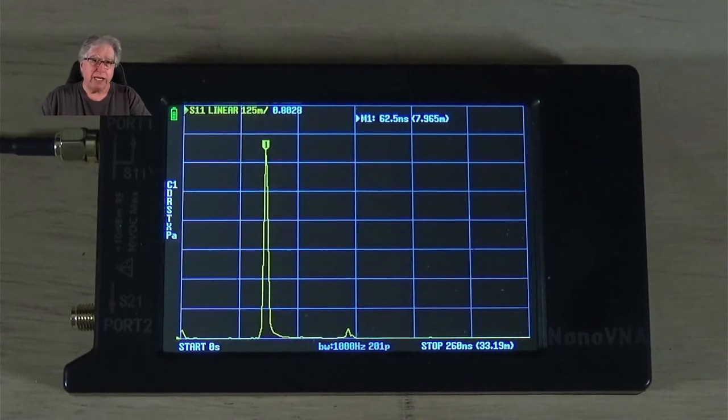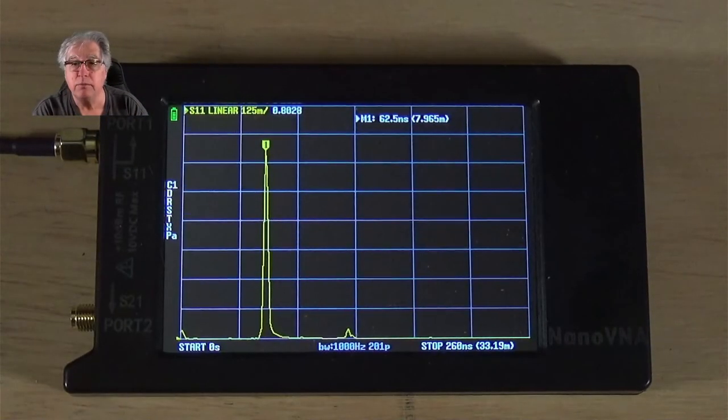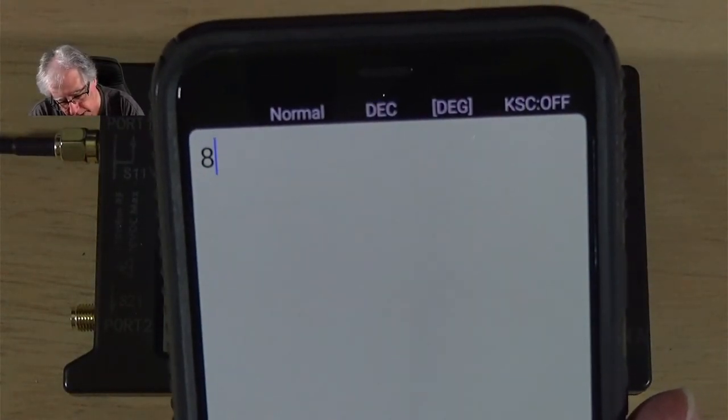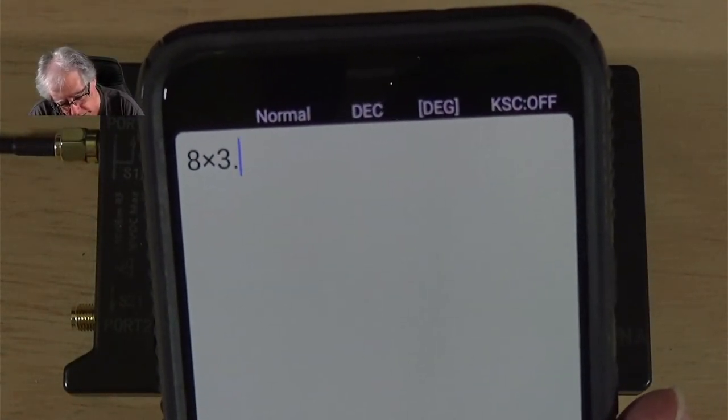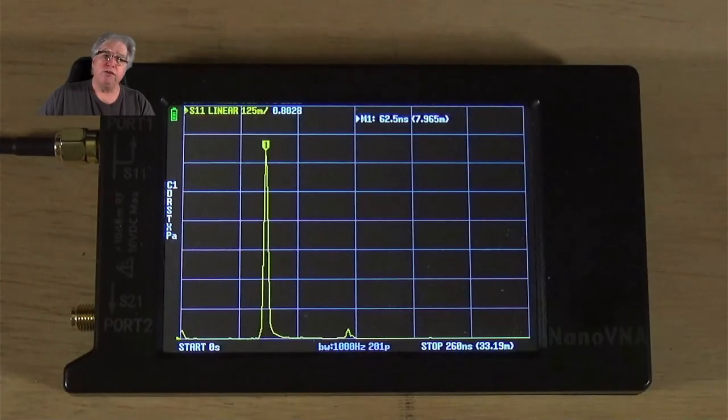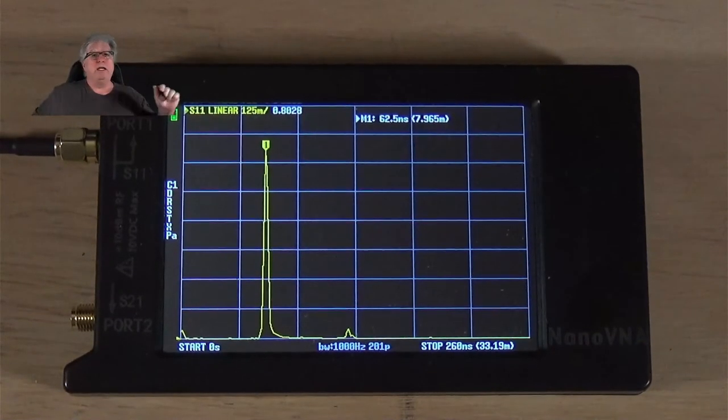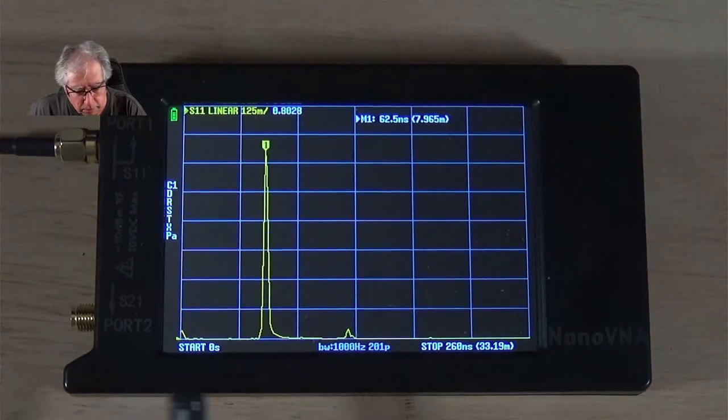What does that work out to in feet? Well, we'll get out our handy calculator, and that's going to be, let's see, what was the number? We'll call it 8 meters, and we'll multiply it by 3.28. It's about 26 feet. That's exactly what the length of this coax, and you know what? This coax apparently doesn't have any opens, but, you know, what are these little bumps here?